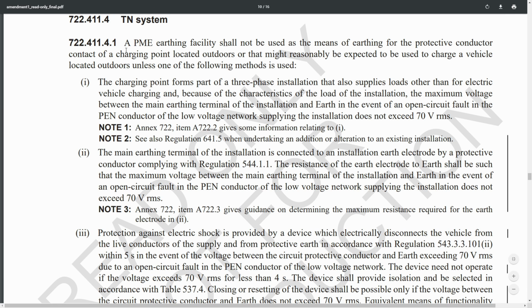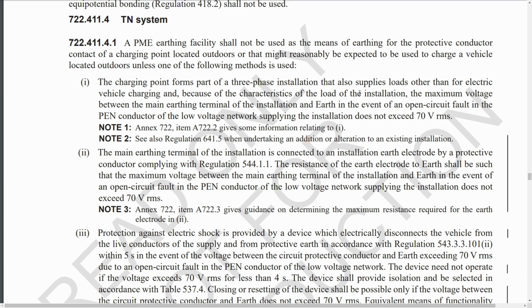Now this top bit is essentially the same. A PME earthing facility shall not be used as the means of earthing for the protective conductor contact to a charging point located outdoors, or that might reasonably be expected to be used to charge a vehicle outdoors, unless one of the following methods is used. And previously there were 3 of these methods, 2 of which were implausible and impossible, and the other one of which was doable but not particularly useful.